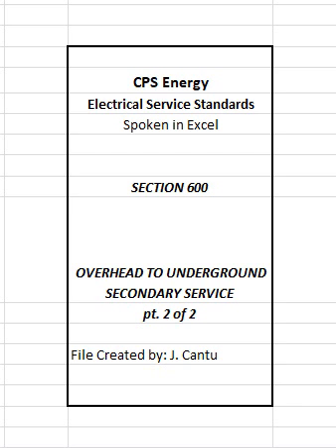2. Sleeves shall have a minimum of 24 inches of cover on top of conduits in private properties and a minimum of 36 inches of cover in public right-of-way unless otherwise specified by CPS Energy. 3. Sleeves shall extend a minimum of 12 inches on each side of sidewalks, driveways, and parking lots, and a minimum of 24 inches if located under streets.